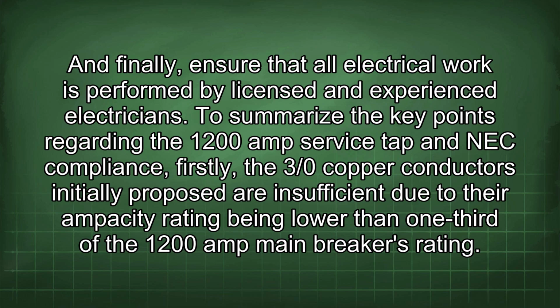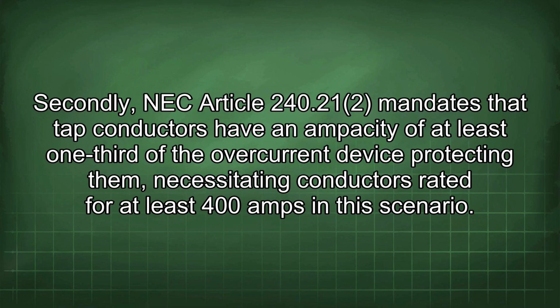To summarize the key points regarding the 1200 amp service tap and NEC compliance, firstly, the 3/0 copper conductors initially proposed are insufficient due to their ampacity rating being lower than 1/3 of the 1200 amp main breaker's rating. Secondly, NEC Article 240.21 mandates that tap conductors have an ampacity of at least 1/3 of the overcurrent device protecting them, necessitating conductors rated for at least 400 amps in this scenario.